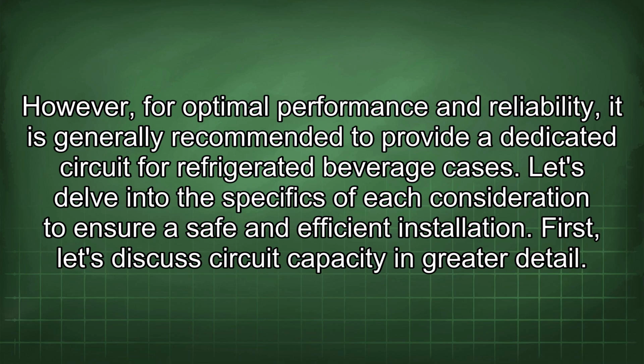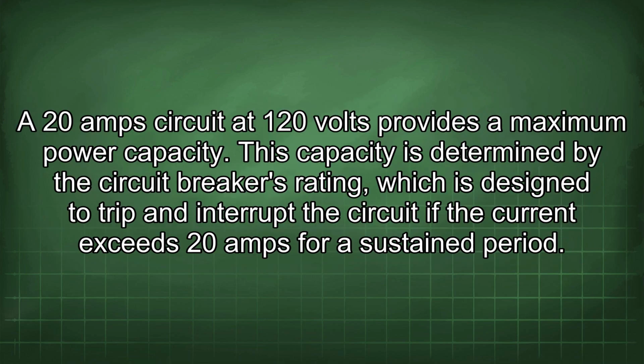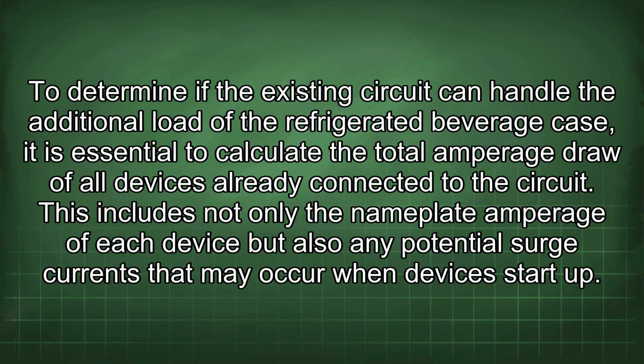First, let's discuss circuit capacity in greater detail. A 20 amp circuit at 120 volts provides a maximum power capacity. This capacity is determined by the circuit breaker's rating, which is designed to trip and interrupt the circuit if the current exceeds 20 amps for a sustained period. To determine if the existing circuit can handle the additional load of the refrigerated beverage case, it is essential to calculate the total amperage draw of all devices already connected to the circuit.